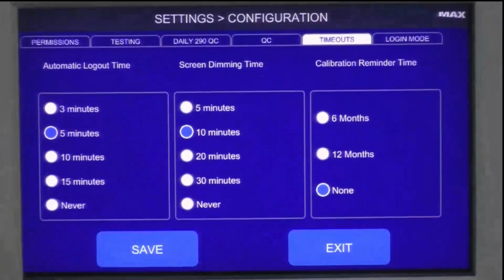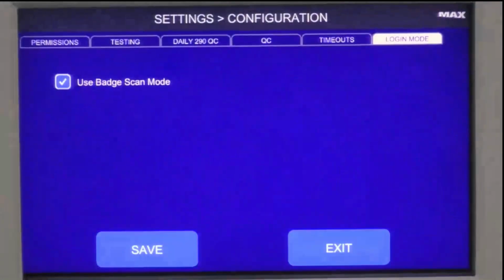These are timeouts. So when that screen timed out earlier, when I was trying to show you the menu, I inconvenienced myself with a timeout there. And then this is the badge scan mode option. So this is how I was able to log in with my badge. When you create a user profile, instead of asking you for a password, it's just going to ask you for a badge scan. So if you have a barcode or a QR code or something on your hospital badge, you can actually use that to log in and create your user profile using that barcode or QR code on your hospital badge. So that's a configuration menu.